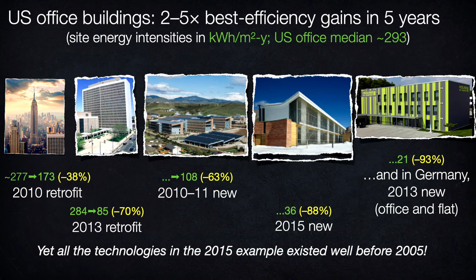As in the Empire State Building, where we first set up a window factory on a vacant floor to remanufacture all 6,514 units from double glazing into super windows that pass light through but block heat. That plus better lights and office equipment and so on cut the maximum cooling load by a third.